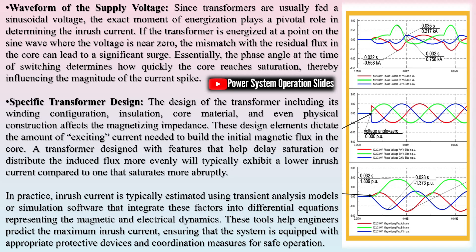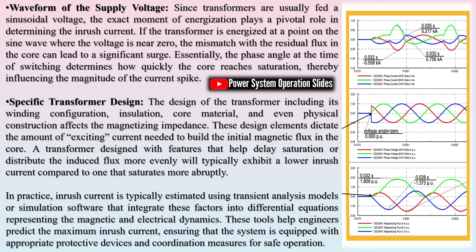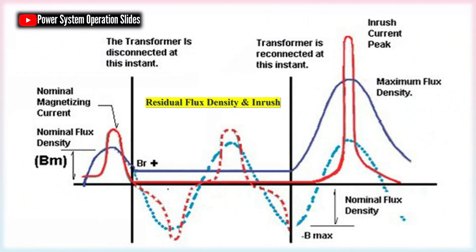Effects of inrush current: Inrush is a normal occurrence when you first energize a transformer. However, in extreme cases, inrush can cause protection devices to trip or even overload the power system or connected equipment.